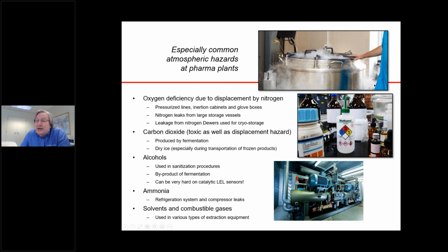If you have a loss of power or a loss of ventilation, or your ventilation just for some reason becomes ineffective, or if you have a break in the plumbing that is introducing the nitrogen into the dewar, or the piping that is taking either pressurized nitrogen or liquid nitrogen through the facility, all of those sources of leakage can result in an oxygen displacement.